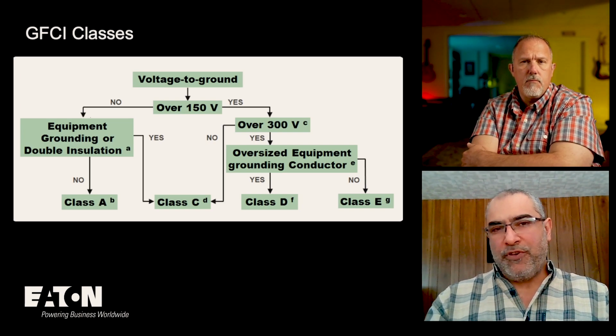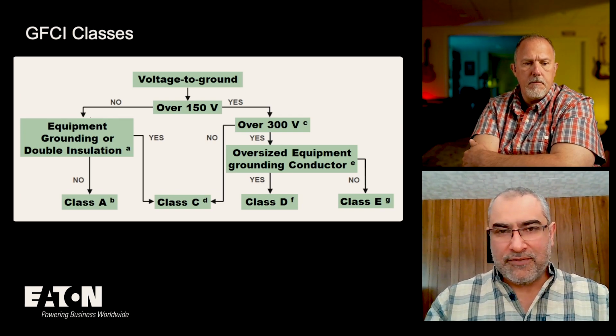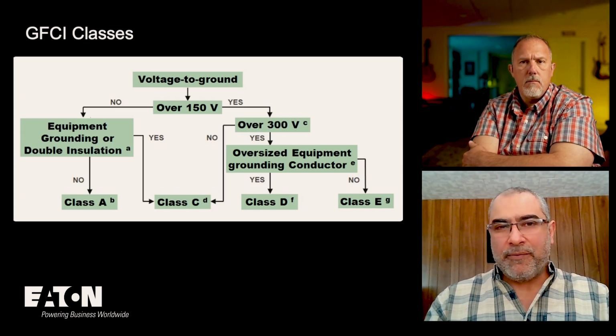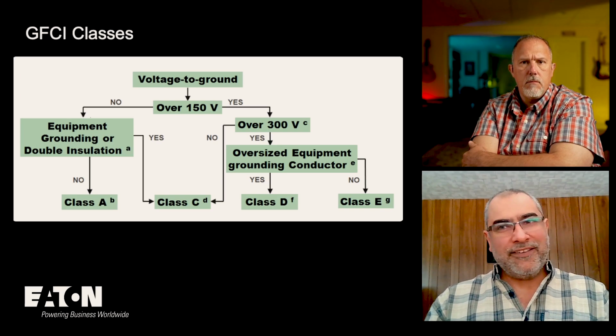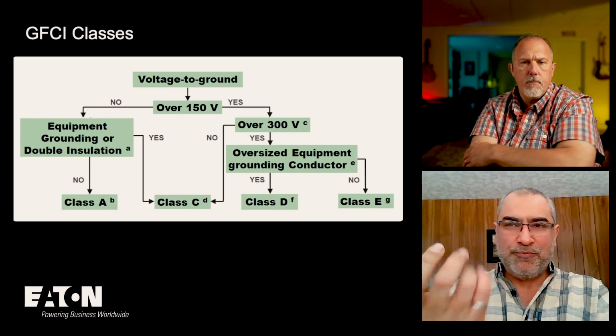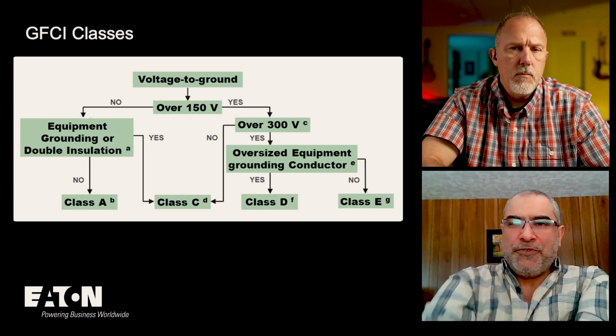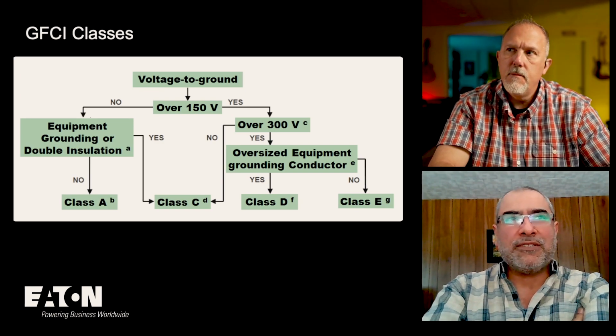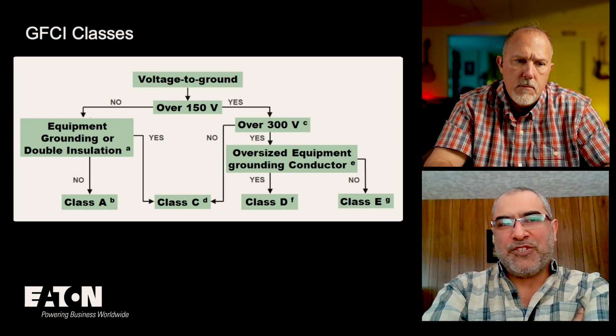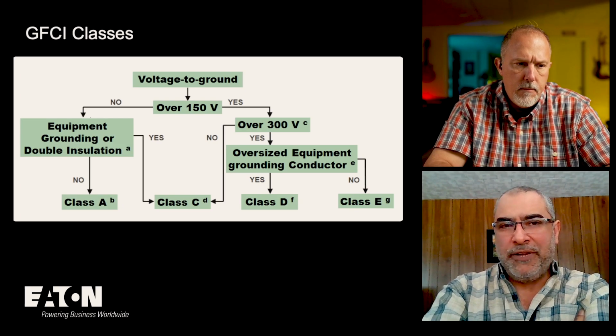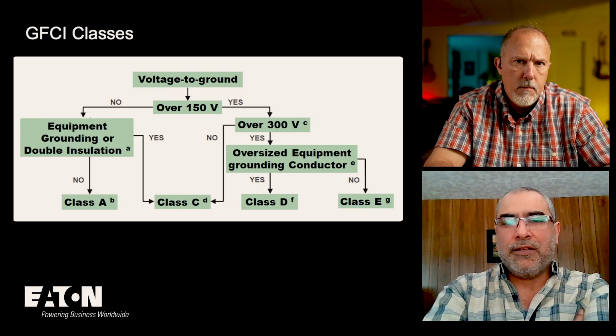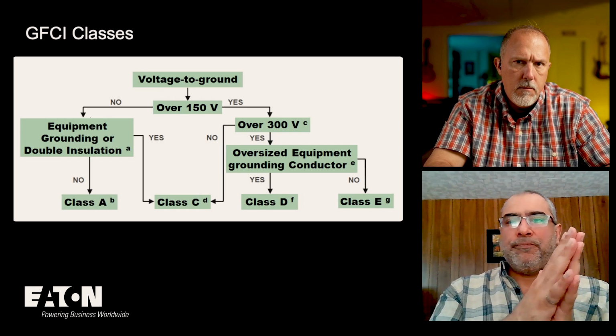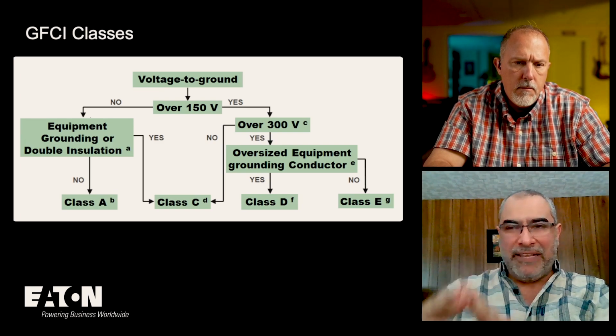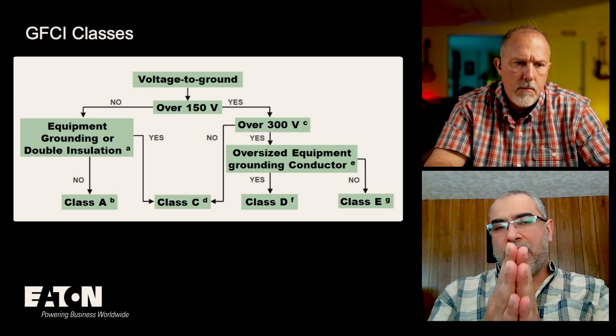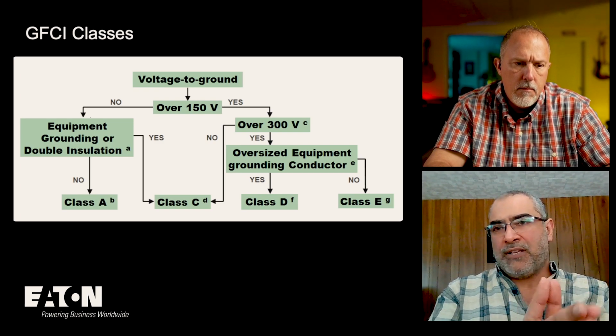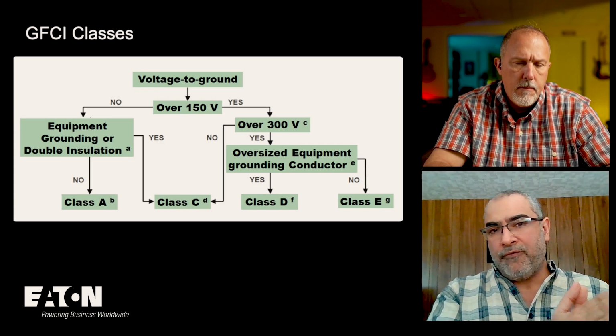Yeah, because when I was involved in designing the first of these devices, we called them industrial GFCIs. This is not the term that UL uses; it's special purpose. Right. And I have an issue with special purpose, because maybe it's a good time to discuss this. Special purpose is not a very good terminology, in my opinion, because it has the connotation that they're only used for special applications, which is not true. They can be used in any application that you use a Class A for, provided that the voltage is right.